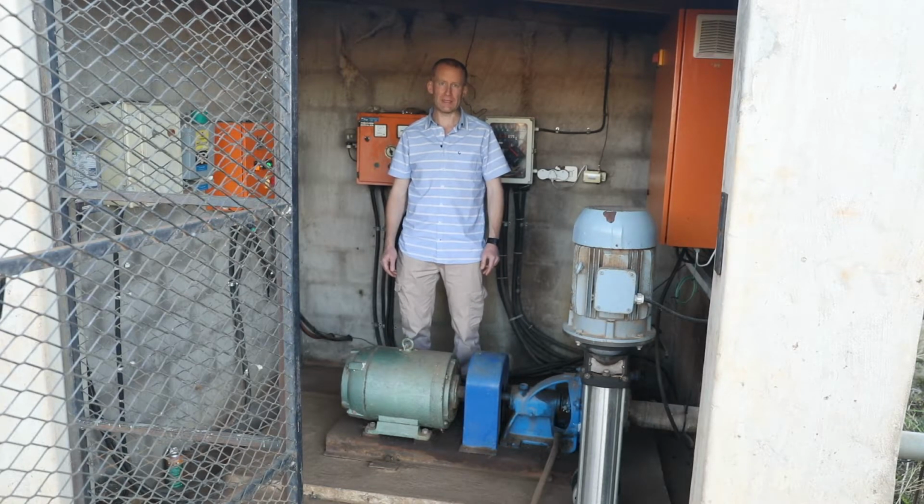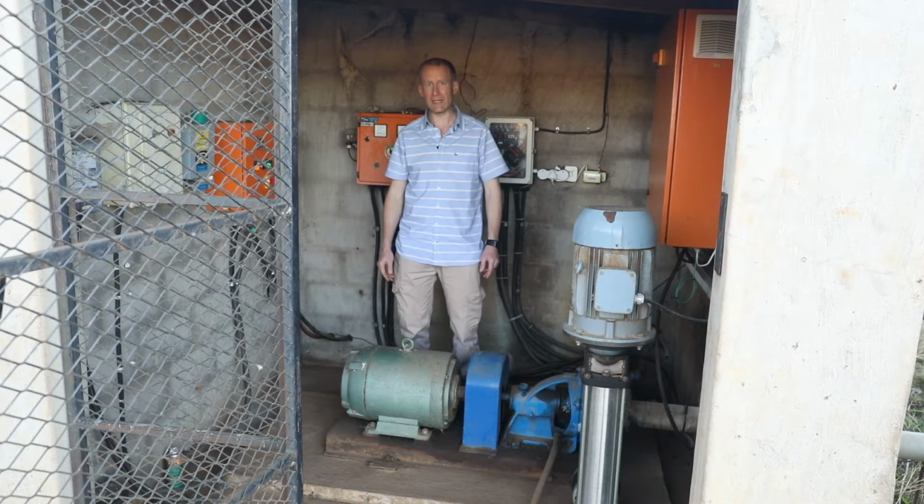When the pivot is facing uphill, you can work on a higher power consumption, and so the maximum demand is around 9 kVA. But still, this is a reduction from a 30 kVA maximum demand. This means that more pumps can be placed on the same transformer without overloading the transformer.